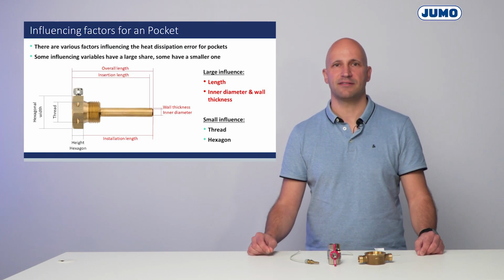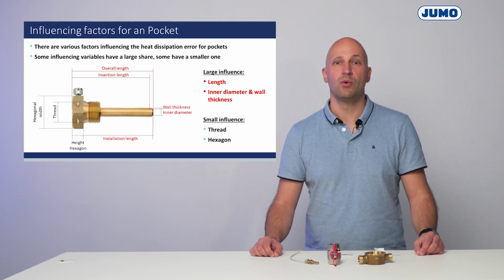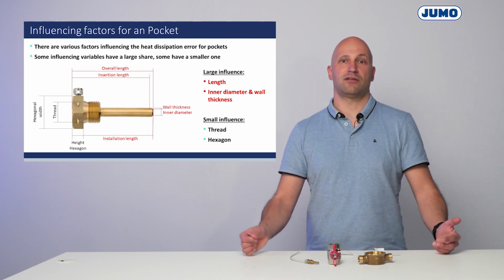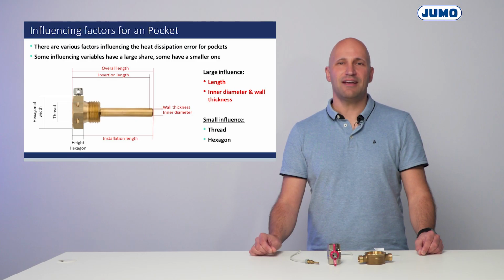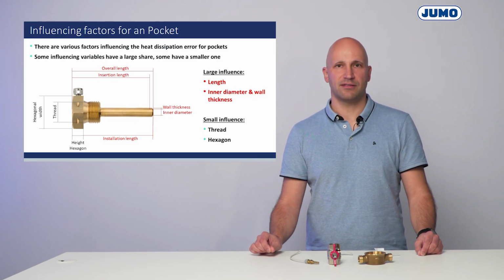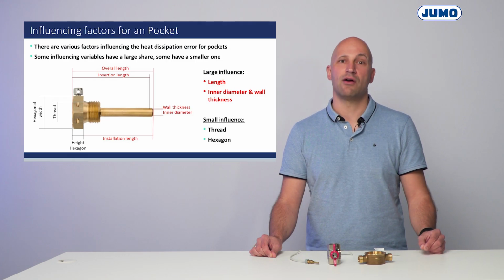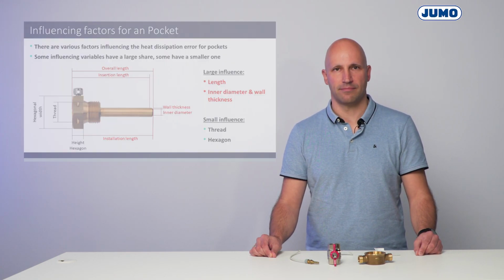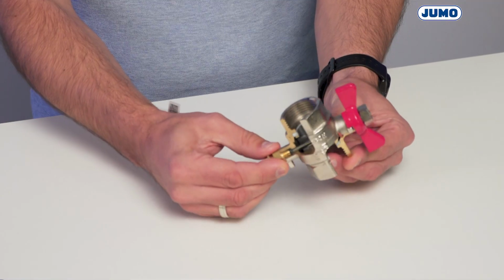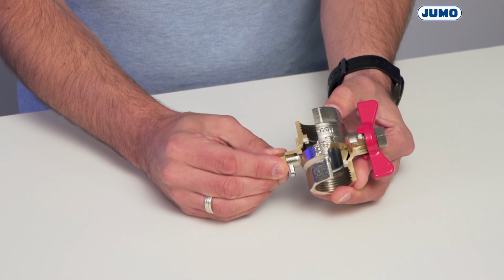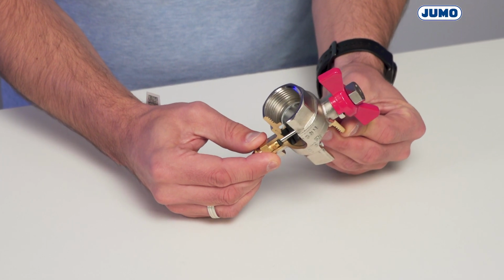In practice, this means that you have to think carefully about which pocket you use, if you need one at all. You should definitely always give preference to direct installation, so that the temperature sensor is directly surrounded by the measuring medium. Such a ball valve with probe installation point, which is even standardized, is suitable for this purpose. Particularly in cooling applications, where the temperature differences are often extremely small, inaccurate measurements can have a significant impact on the billing result.